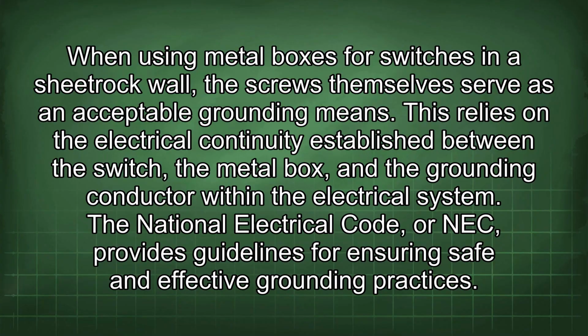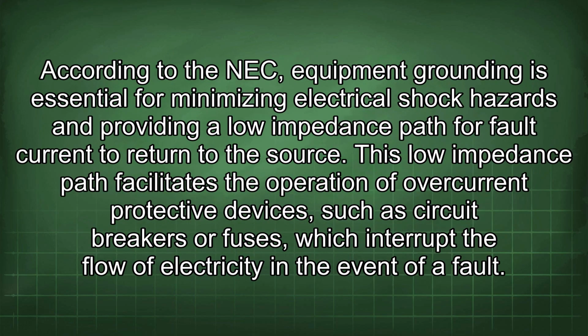When using metal boxes for switches in a sheetrock wall, the screws themselves serve as an acceptable grounding means. This relies on the electrical continuity established between the switch, the metal box, and the grounding conductor within the electrical system. The National Electrical Code, or NEC, provides guidelines for ensuring safe and effective grounding practices. According to the NEC, equipment grounding is essential for minimizing electrical shock hazards and providing a low impedance path for fault current to return to the source.